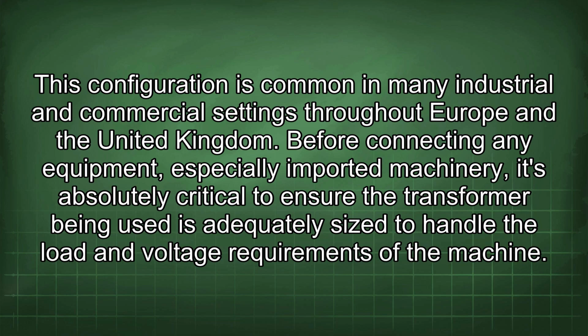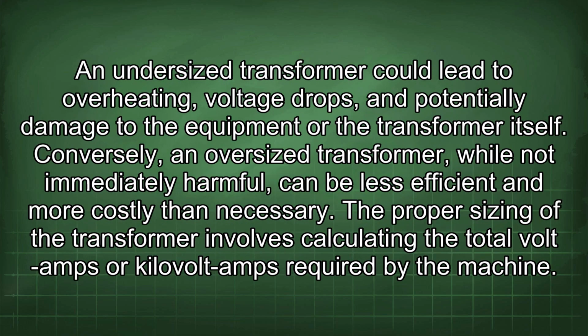Before connecting any equipment, especially imported machinery, it's absolutely critical to ensure the transformer being used is adequately sized to handle the load and voltage requirements of the machine. An undersized transformer could lead to overheating, voltage drops, and potentially damage to the equipment or the transformer itself. Conversely, an oversized transformer, while not immediately harmful, can be less efficient and more costly than necessary.